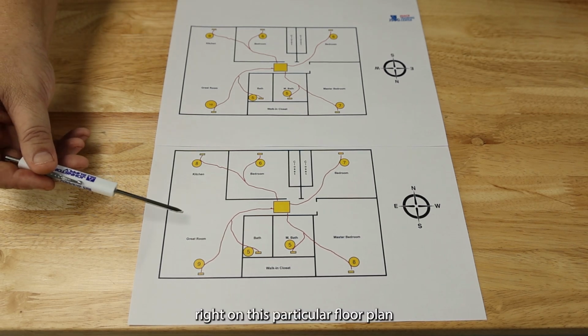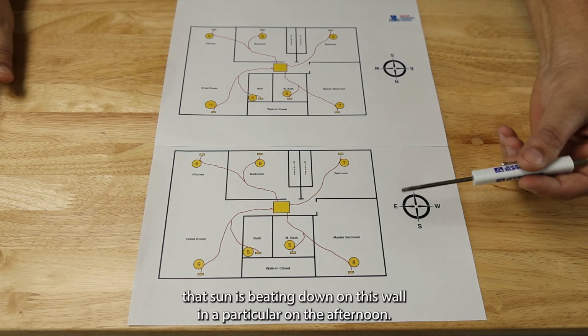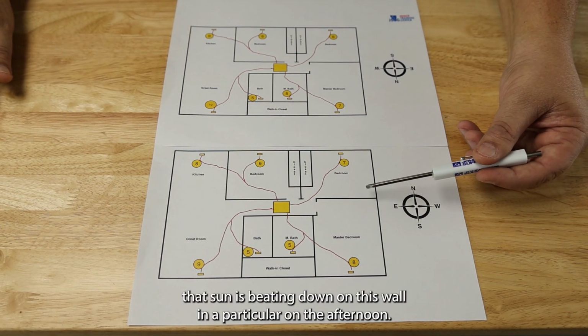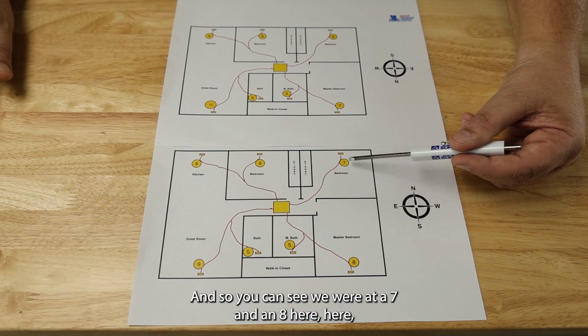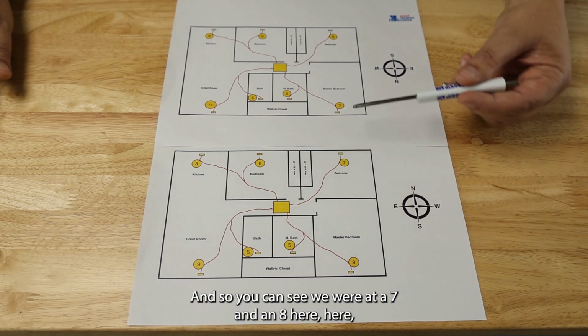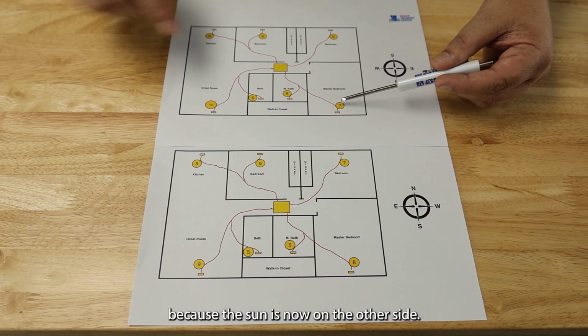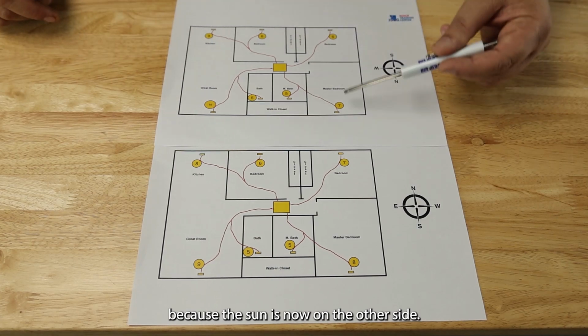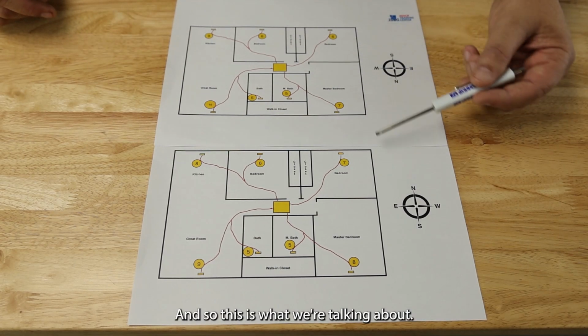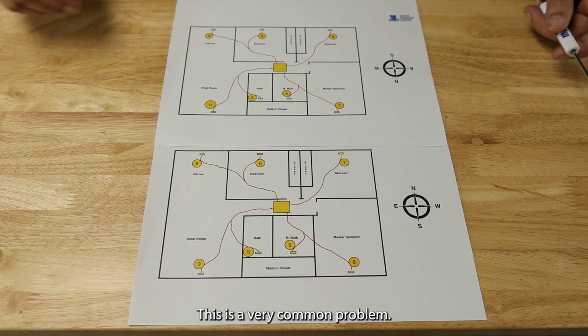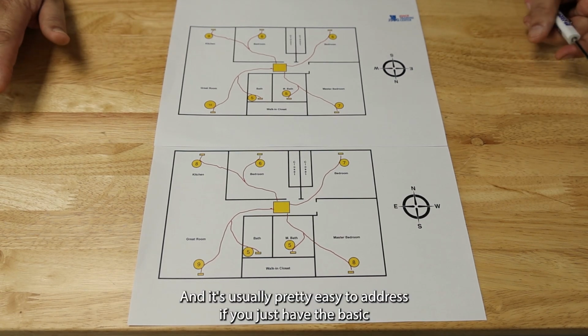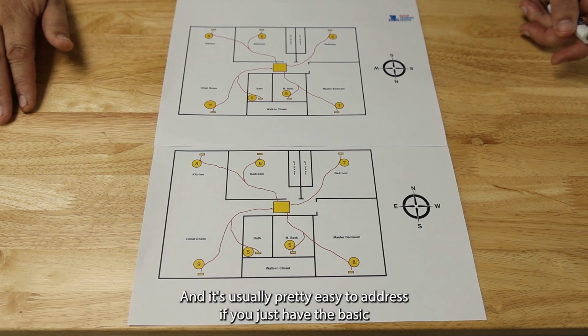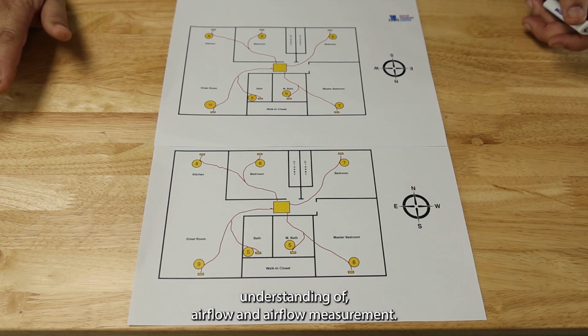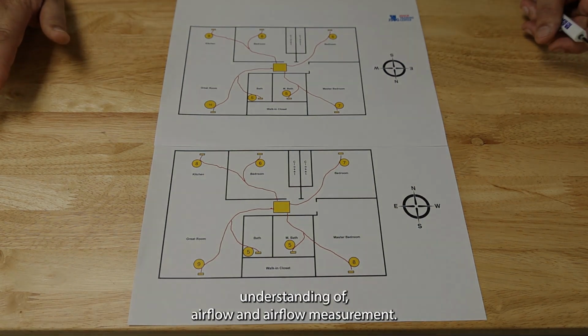On this particular floor plan, that sun is beating down on this wall in the afternoon, and so you can see we were at a 7 and an 8 here because the sun is now on the other side, right? We reduce those, and so this is what we're talking about. This is a very common problem, and it's usually pretty easy to address if you just have the basic understanding of airflow and airflow measurement.